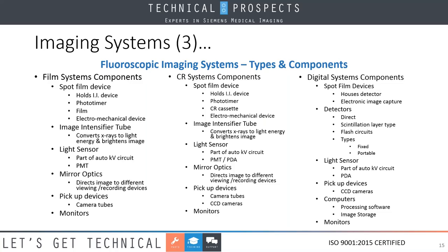You'll also notice that in the early days, we used image intensifier tubes. That's now been replaced by detectors on our modern systems. We always have to have a light sensor in there because this is part of the auto kV circuit, because fluoroscopic images are live images. And as we're going over the patient, we encounter different densities. The light output is going to change, whether it's our tube or a detector.